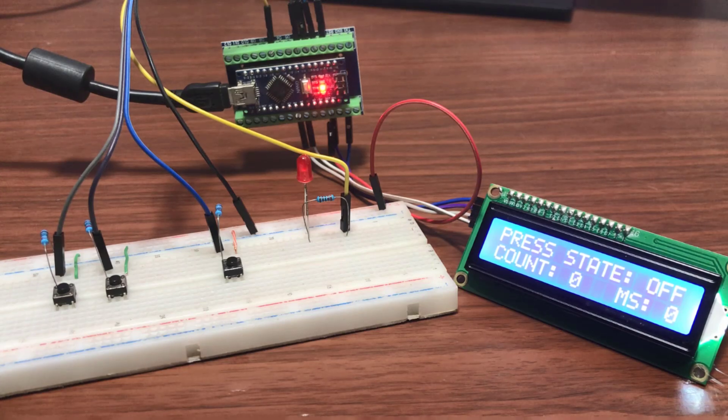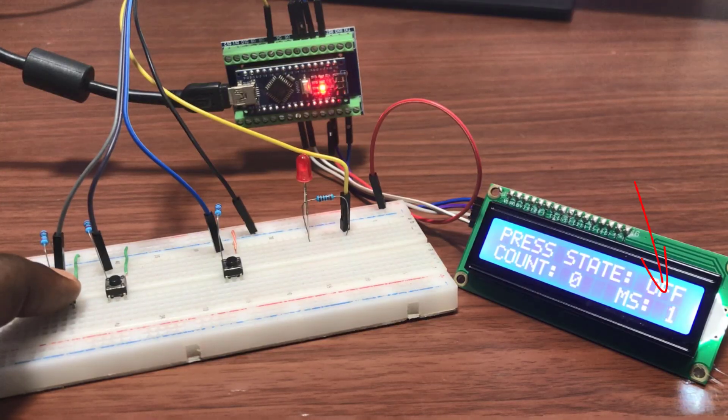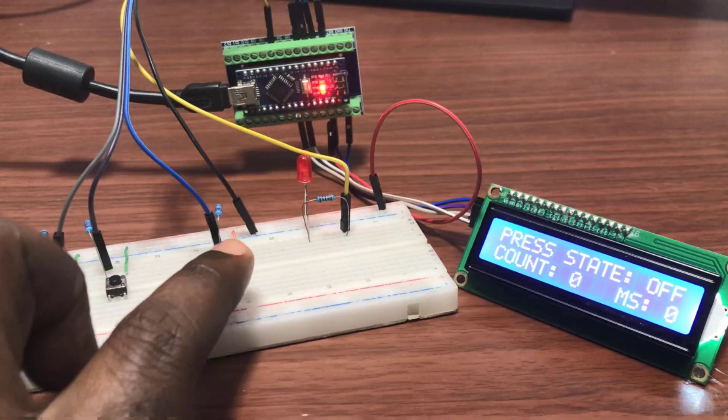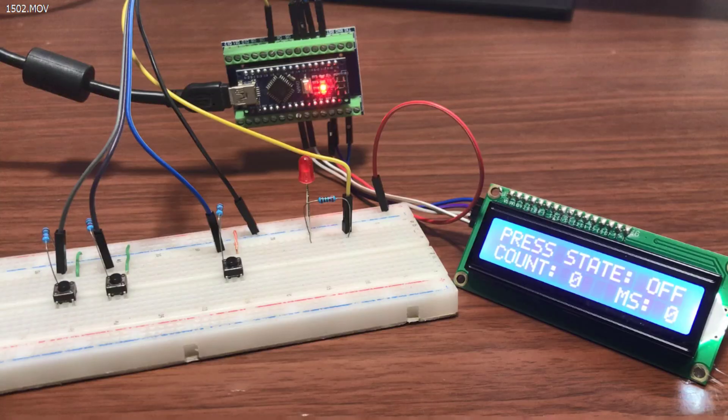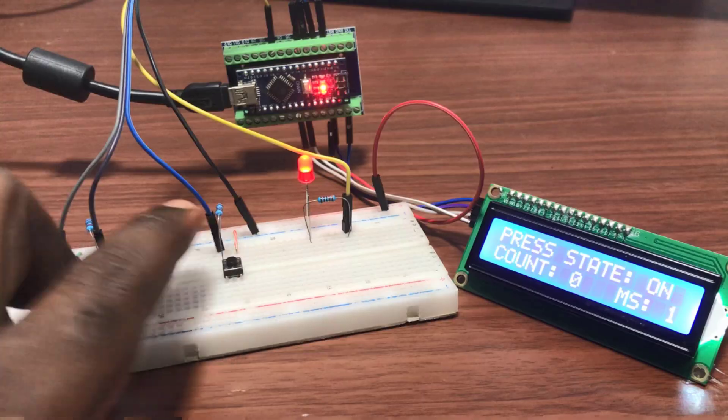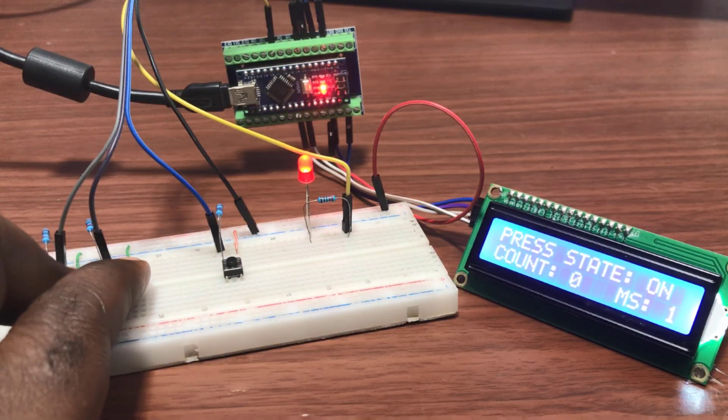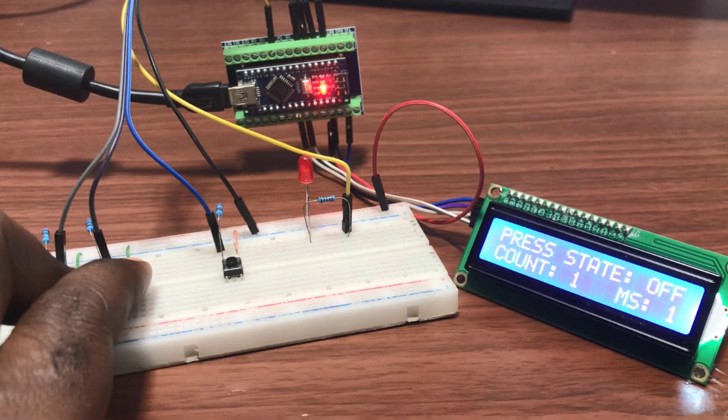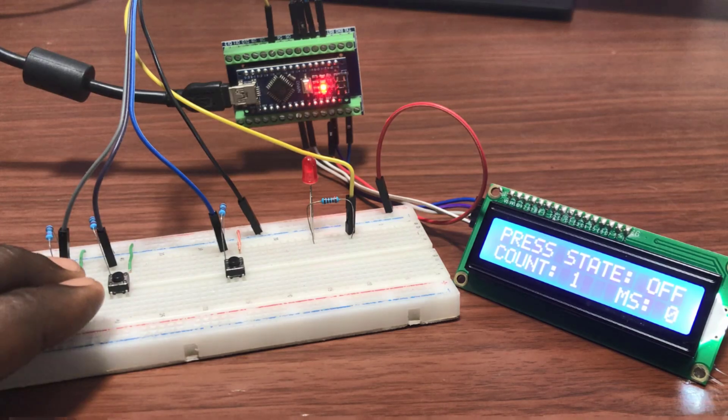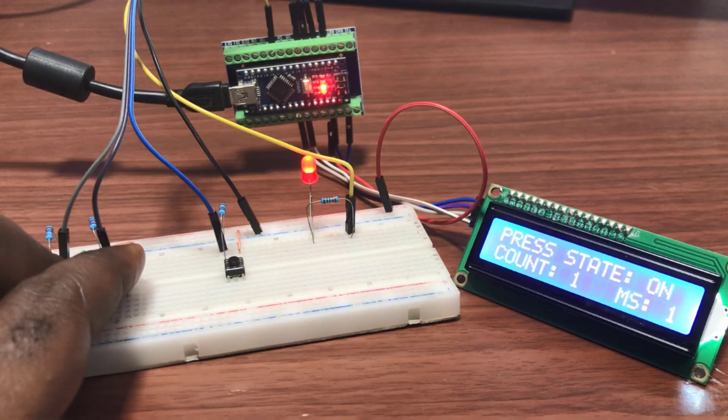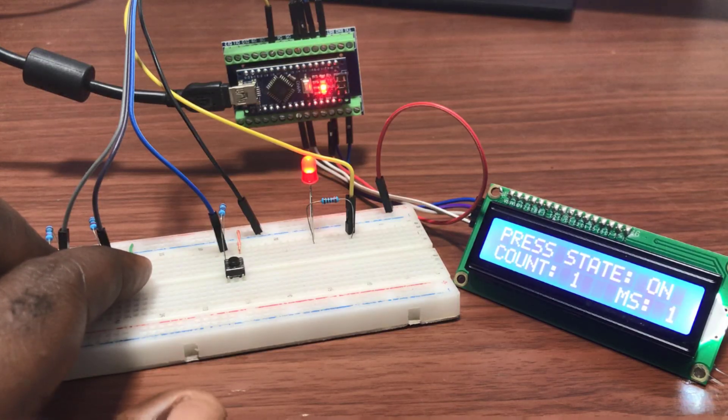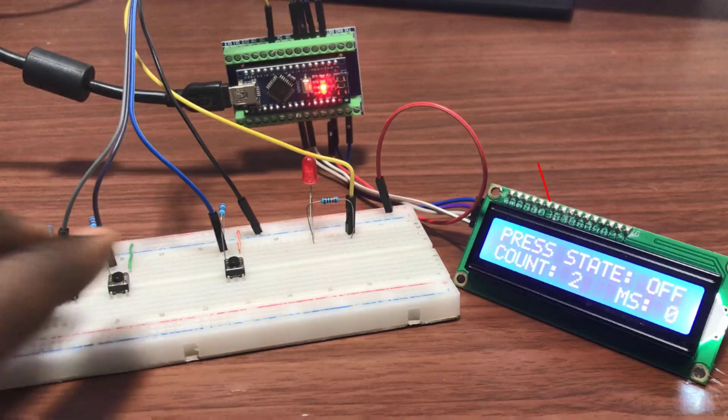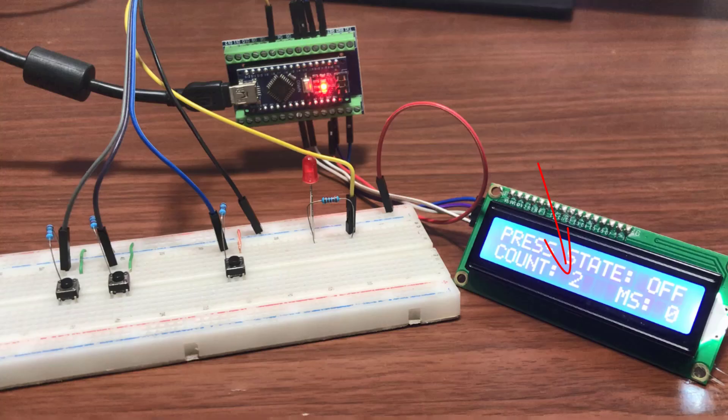And we can see the screen indicating the status of everything on the press. So you can see the press status, we can see the counter, and then we can see the material sensor as well. Now when I press the material sensor, you can see it shows one indicating that there is material. If I release it and press the start, nothing happens because the material sensor has to be active before you can start. So I press it, it shows one. And I press on and it comes on. And then I hold the full extension sensor for 5 seconds. And then we can see that one job is done and the counter shows one. I press on the material sensor again, set the system on, and then hold the extension indicating that there is pressure on the material. And after 5 seconds, the count moves to 2, indicating that a second job is done.